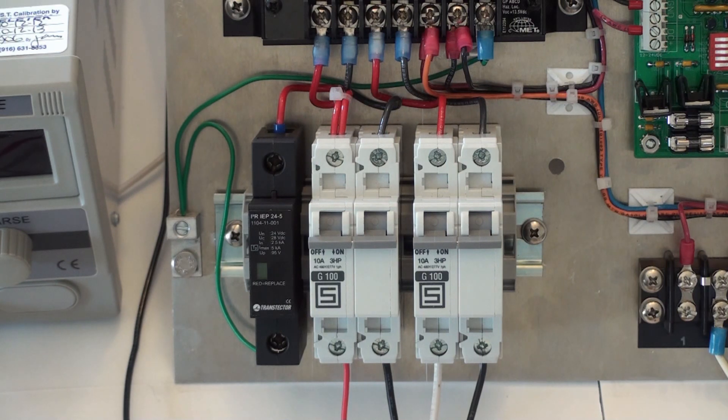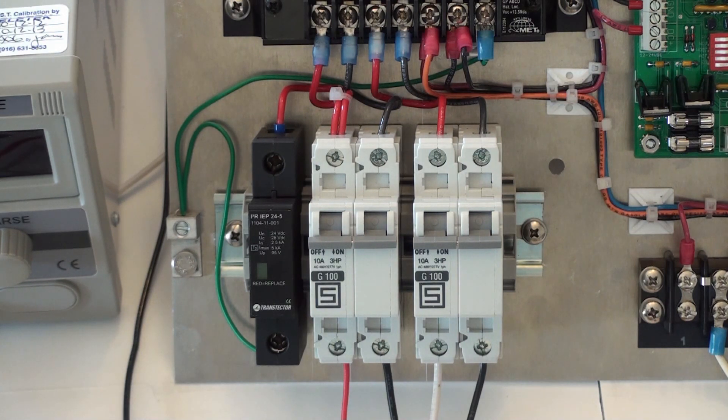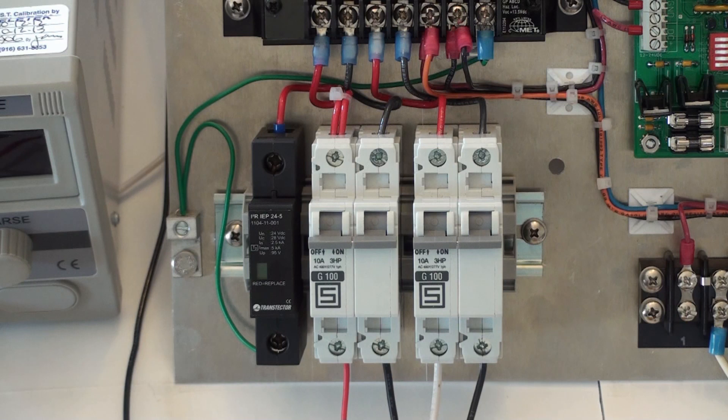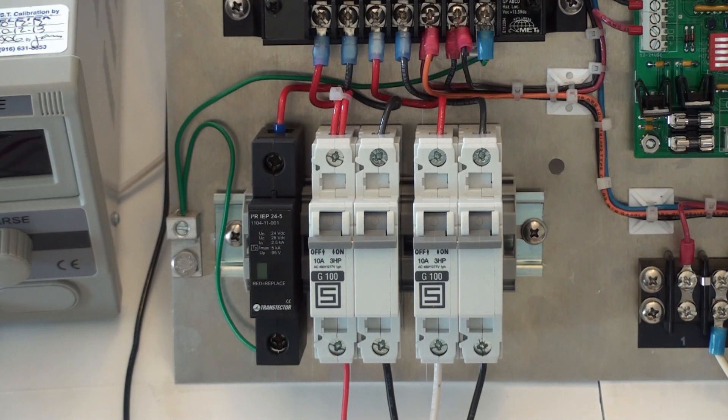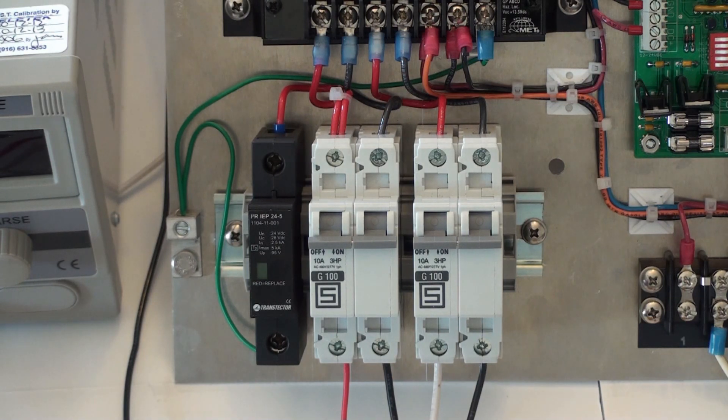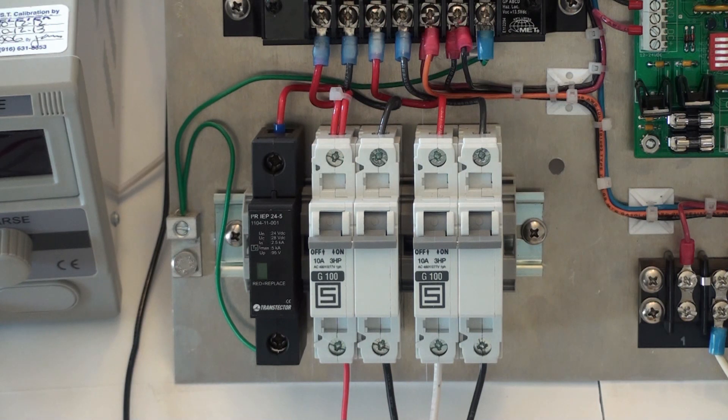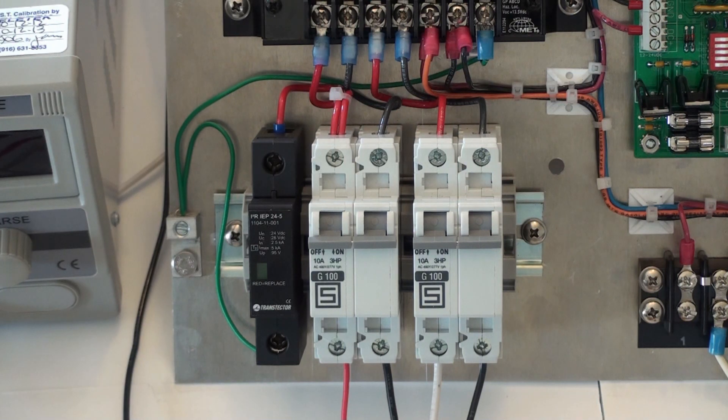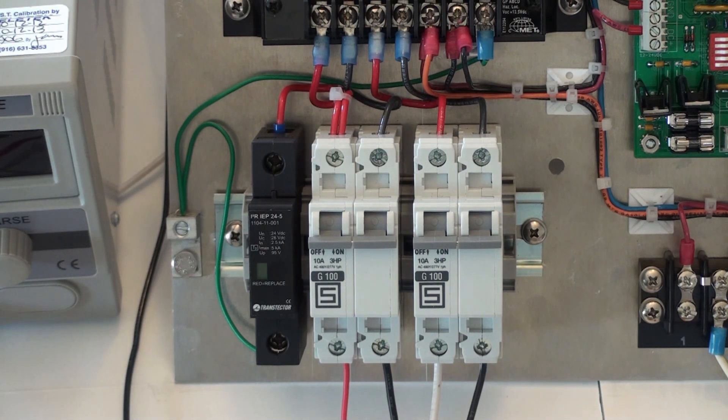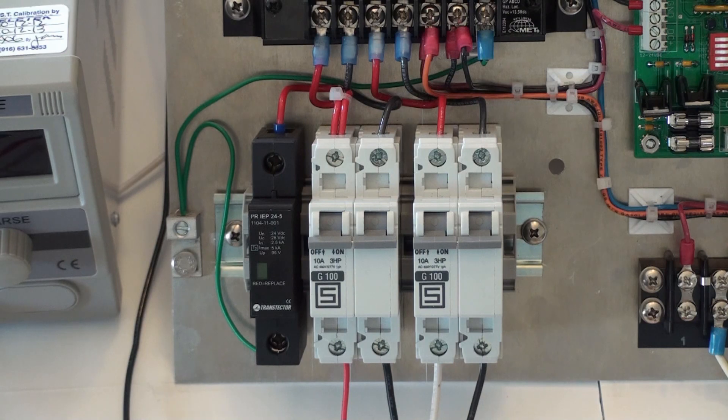The circuit breaker can be tested by first removing its inputs and then running a continuity test. First in the on position we should measure a short circuit, and then in the off position where you should measure an open circuit.